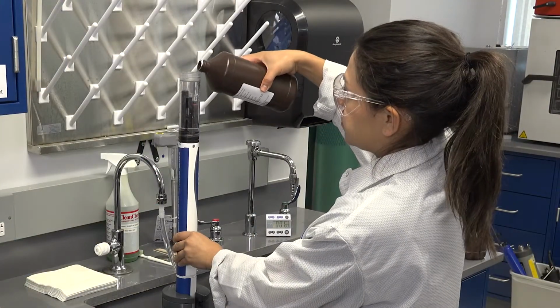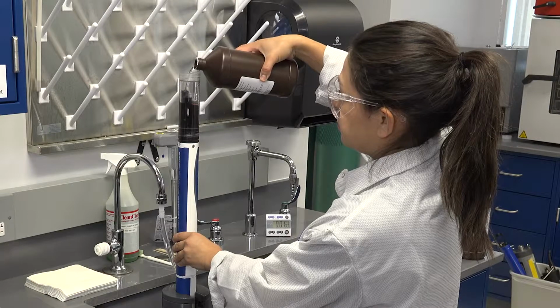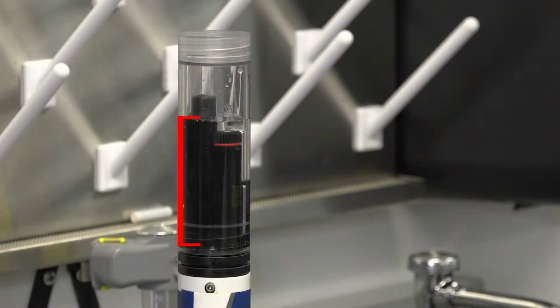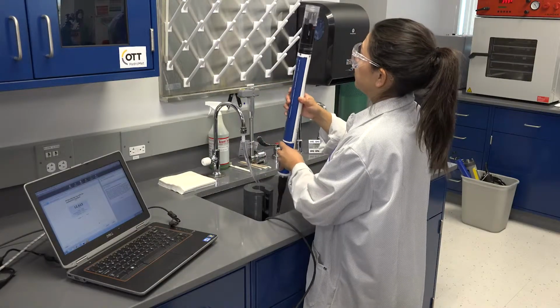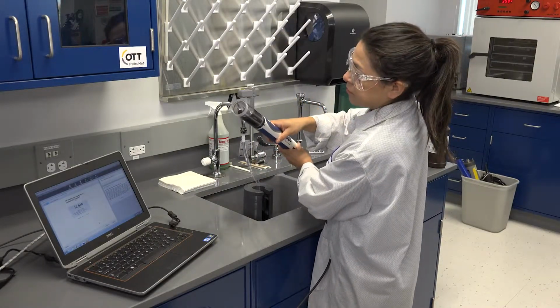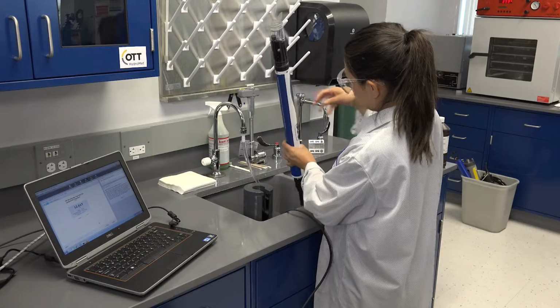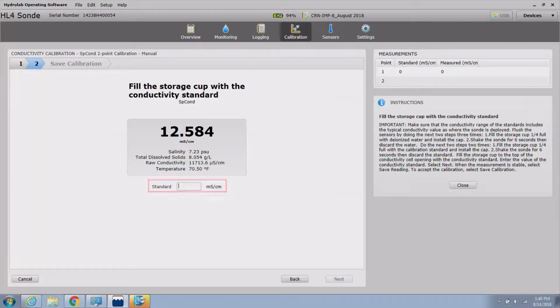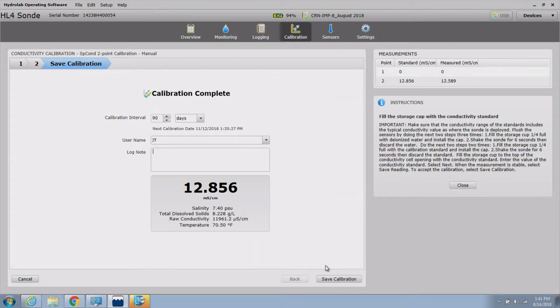Fill the storage cup up with conductivity standard, making sure that the oval hole in the conductivity sensor and the temperature sensor are completely submerged in standard. Be sure to check that there are no bubbles inside the conductivity cell, as these will interfere with the measurement. Enter the value of the conductivity standard into the standard text box. Click Next to proceed. The stabilization process will begin and must complete successfully before the calibration can be saved. To accept the calibration, select Save Calibration.